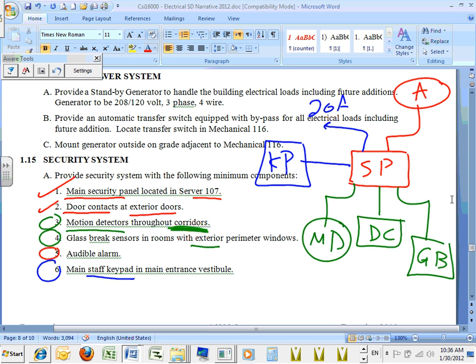So in the past, we did them from the lighting panel. I would put all the system in the lighting panel just to be consistent. But if you put them in the mechanical, and the main, I wouldn't put them in the receptacle panel though. And the main panel, I envision the main panel would be big enough, and these are 20 circuit breakers. I like them to be in a panel that's small.